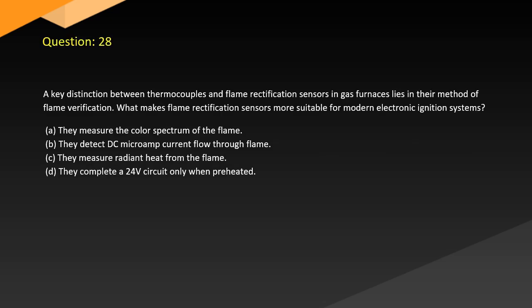Question 28. A key distinction between thermocouples and flame rectification sensors in gas furnaces lies in their method of flame verification. What makes flame rectification sensors more suitable for modern electronic ignition systems? A. They measure the color spectrum of the flame. B. They detect DC microamp current flow through flame. C. They measure radiant heat from the flame. D. They complete a 24-volt circuit only when preheated.